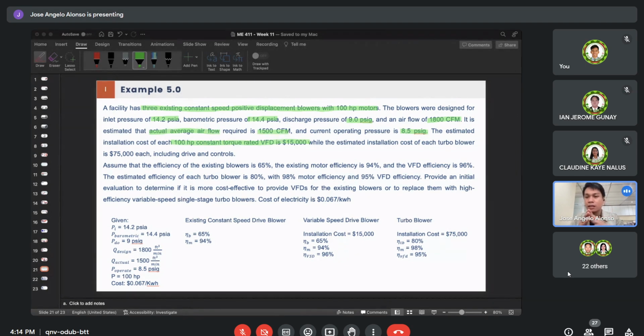Alam naman natin na yung VFD, the variable frequency drive, class, ang kanyang purpose is to vary the speed depending on the required flow rate. Okay? So kung nagre-require lang ng 1,500 CFM, pag nag-install tayo ng VFD, yung rotational speed ng motor natin, mababawasan yan para makapag-supply lang ng 1,500 CFM. And correspondingly, yung operation cost ng ating motor will be reduced as well kasi nga hindi siya at peak capacity, hindi 100% yung kanyang rotational speed. Okay? So, i-compare natin yung cost reduction due to that power reduction, yung power saving ng pag-install ng VFD.